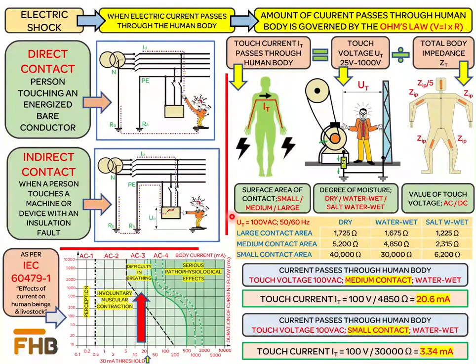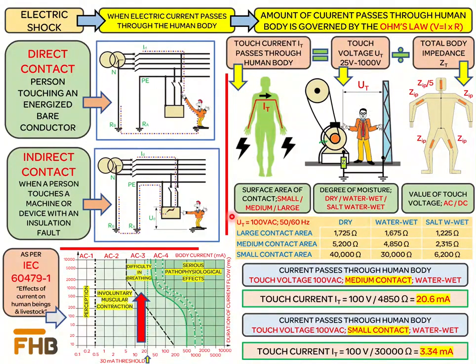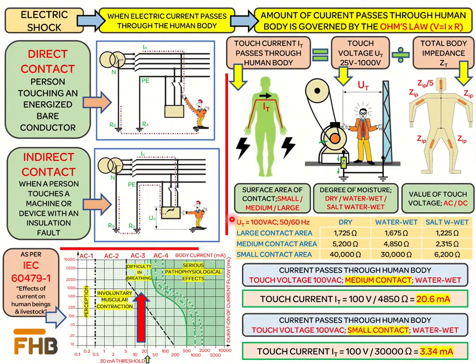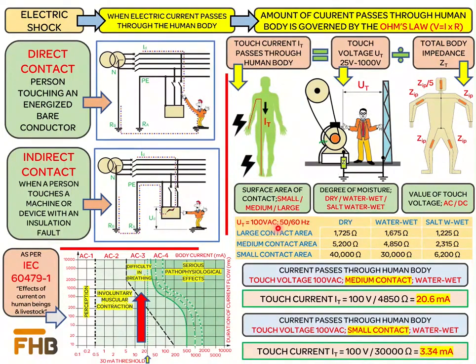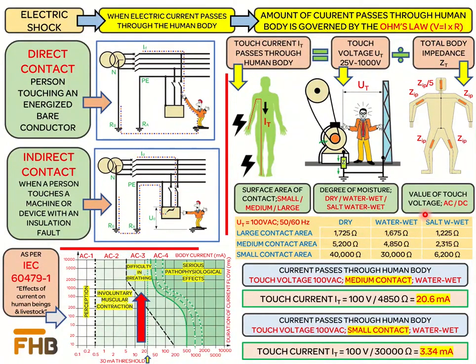IEC 60479-1 defines the values of total body impedance under tables 1 to 9. These values are defined for AC voltages with 50 or 60 Hz frequency. To develop further understanding of how body impedance changes with surface area of contact and degree of moisture, we have made a comparison here, considering a touch voltage of 100 V AC at 50 or 60 Hz. We can see that body impedance decreases with an increase in moisture content, and is greater with smaller contact surfaces, decreasing as the contact surface increases.